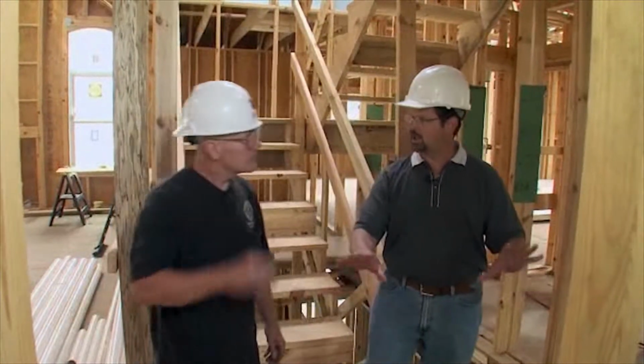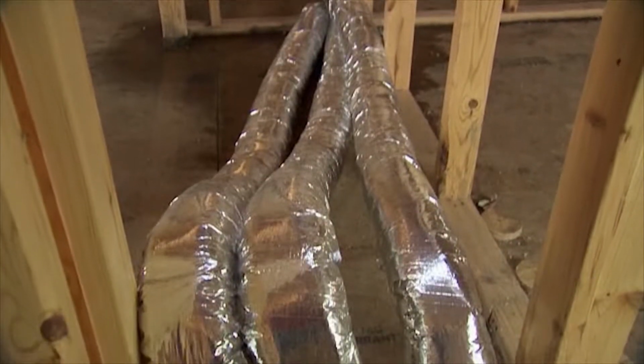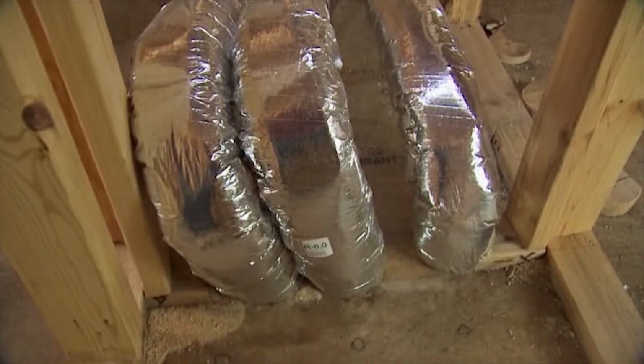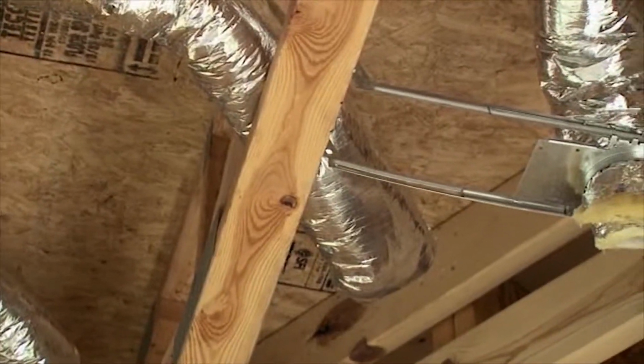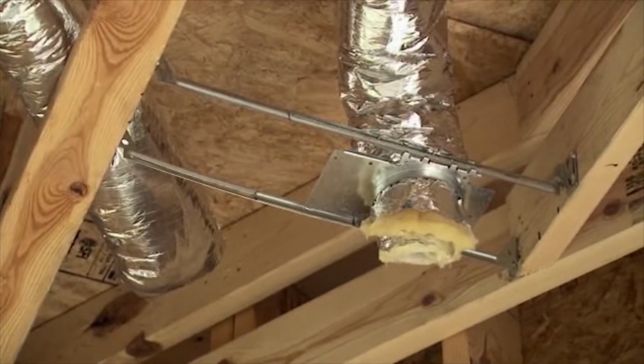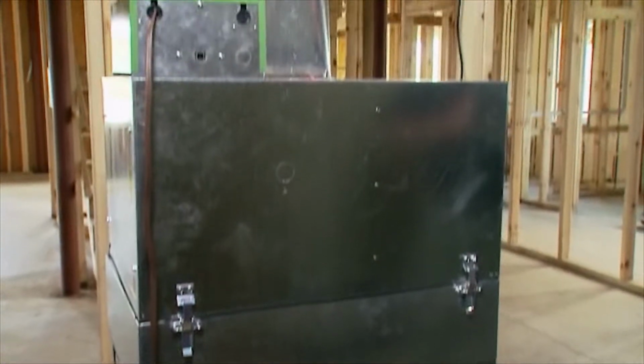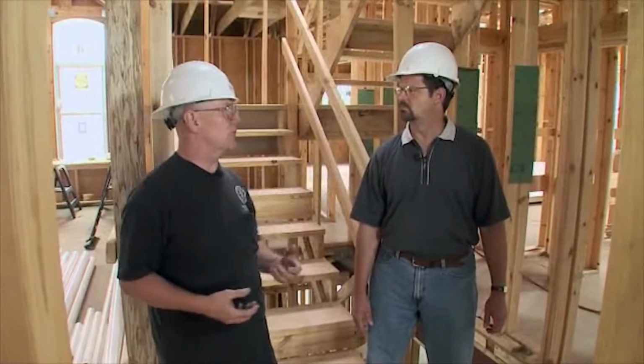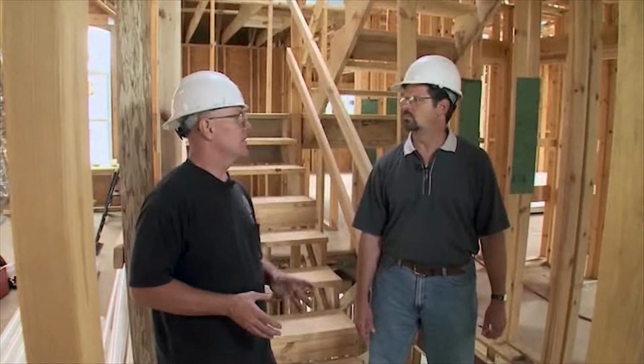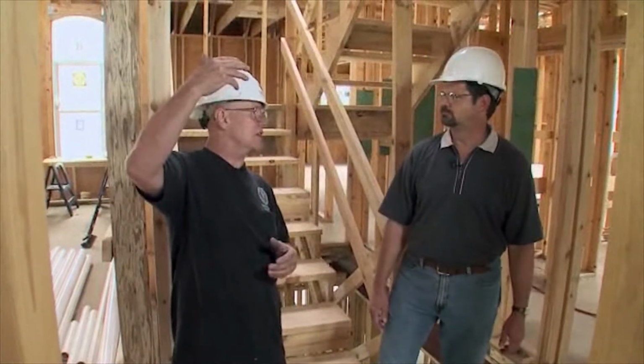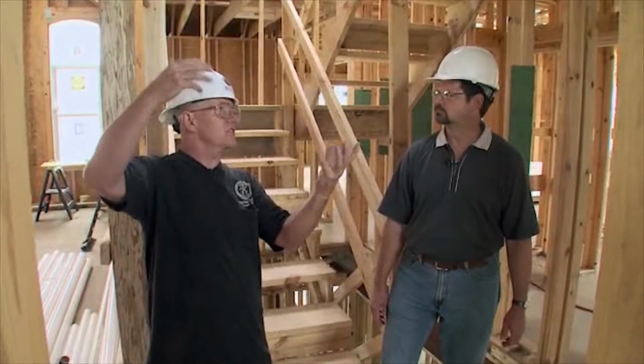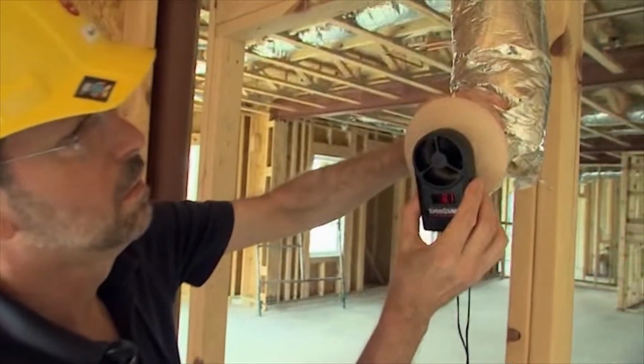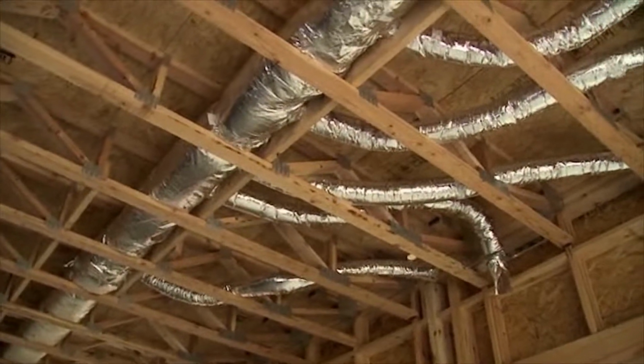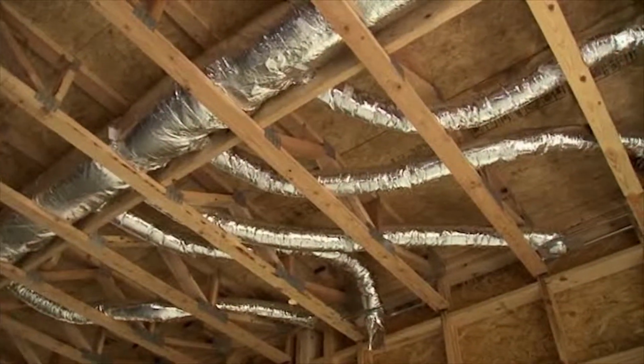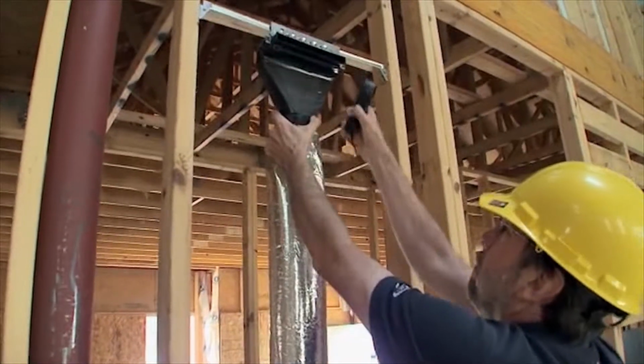Now all this ties back to the mechanical room that's below here, right? Everything's going right into the mechanical room, whereas our returns are going to run down into the ceiling, with grills put on the ceiling, with the master room downstairs being a plenum room, and a master return going into the units in the mechanical room. It stratifies much better in a room like this with a high velocity system. Whereas with our lower velocity systems, we have to have a return in every single room in order to get that heat off the ceiling and the cool from the floor to draw up. With this system, it mixes pretty evenly in the room, so it works real well. So it should be a nice comfort level regardless of time of year. Absolutely. No matter what the ceiling height or level, it should be a nice mix of air. Easier on the units, actually.